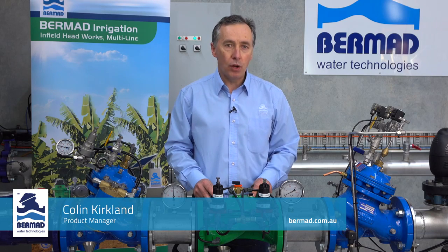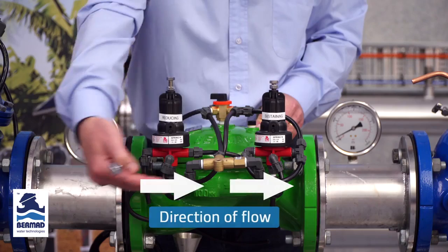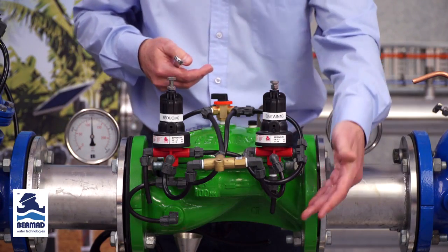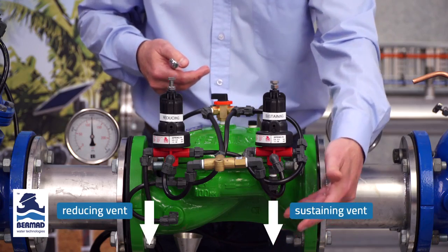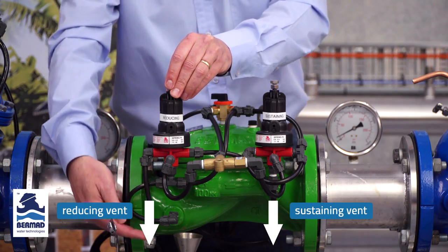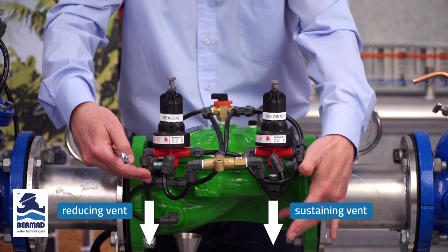This is an instructional video on how to set the Bermad model 423 pressure sustaining and pressure reducing valve. For the purpose of the demonstration, the water is flowing from left to right. The reducing pilot is on the left-hand side, which vents out through the bottom of the pilot, and the sustaining pilot is the pilot that vents out through the side and senses the downstream pressure.